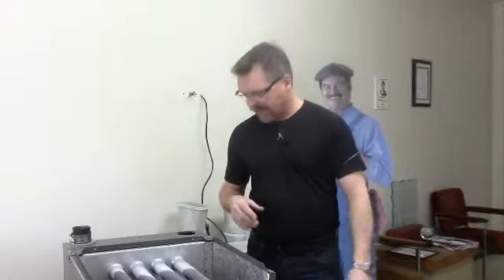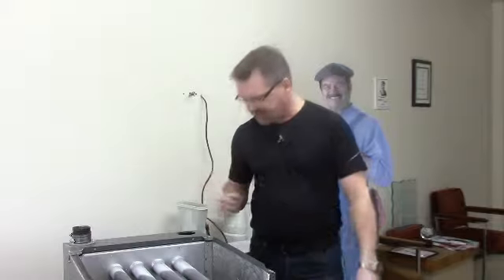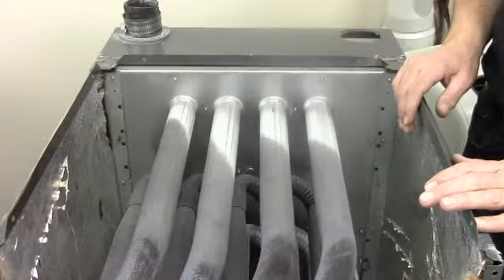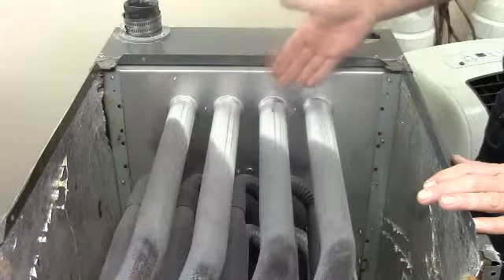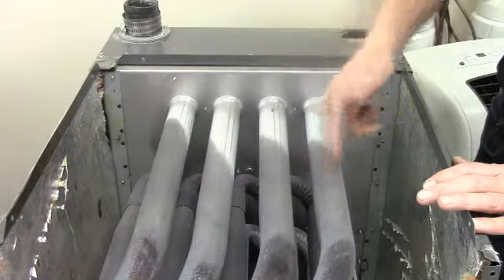One of the crucial things that we look at is the heat exchanger. So I opened up an inspection hole and I took my scope and took a look inside, and initially I saw a lot of what they call hot spots, where the heat exchanger itself has changed color and has gotten quite dark. That's a sign of overheating. And then I found a very small crack on the inside of this heat exchanger. But because of all the hot spots, and it progressively got worse as it got back, I needed to take a closer look. So again, I took my scope around to the back, and you can see where we actually had a catastrophic failure of the heat exchanger. It had completely blown out. I can stick my entire little finger inside the heat exchanger here at the back.